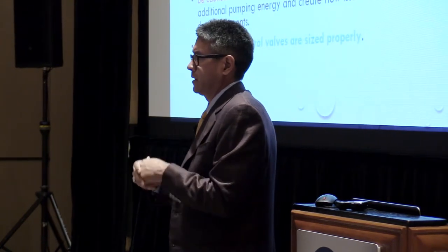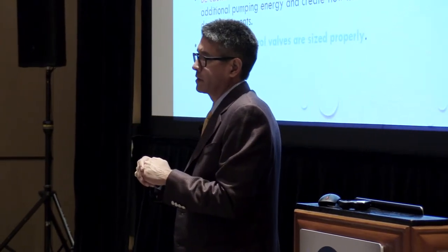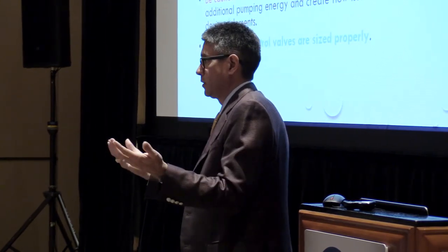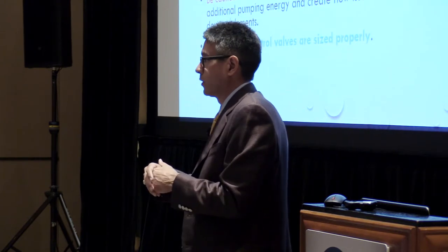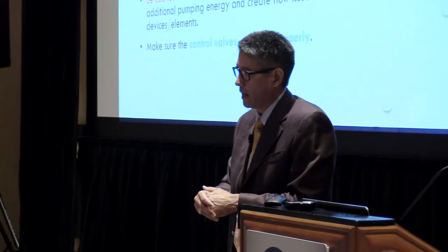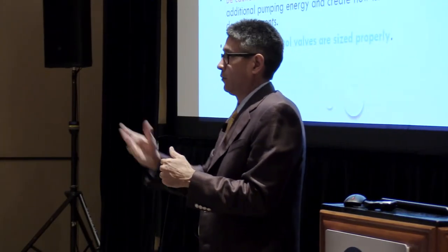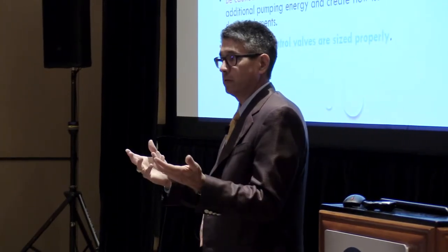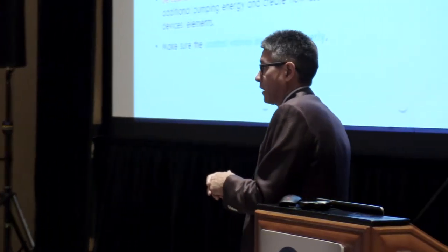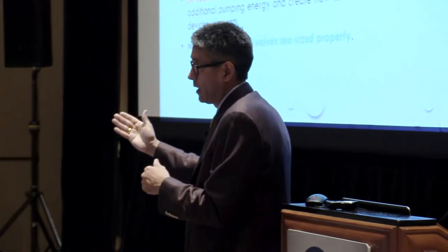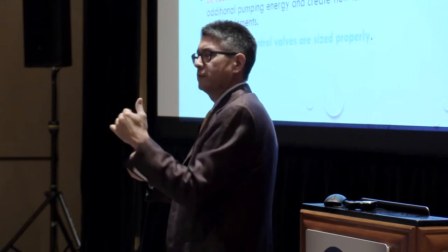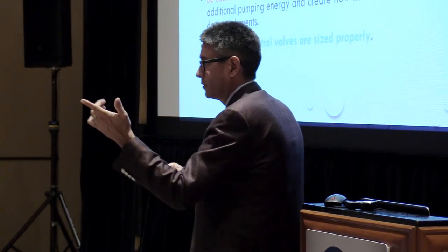Biggest, I'd say, downfall I hear about automatic flow limiting devices is flexibility. Once you put it in, your cartridge is in there, and it's set for 20 GPM, you're limiting down to 20. You can get less than 20 if you underflow it, which is fine. But if you want to get more than 20, you're going to have to change the cartridge out or possibly change the valve out. So that's usually the biggest hiccup. Because keep in mind, if you have a manual balancing valve set for 20 GPM and you don't have enough flow going to that, it's underflowed. Underflowed? It doesn't have as much flow either.